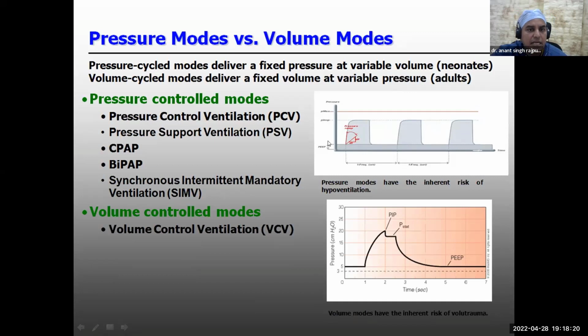First, we'll understand that in pressure modes, the pressure is plateaued, right? So what we do is we deliver flows in such a way that pressure does not cross the level that we have decided. So suppose I tell the ventilator to ventilate the patient with a pressure of 15. So this plateau will continue to remain at 15. The pressure will increase up to 15. How will the pressure increase? The flow will take place, and the flow will increase suddenly to push the pressure suddenly up to 15.